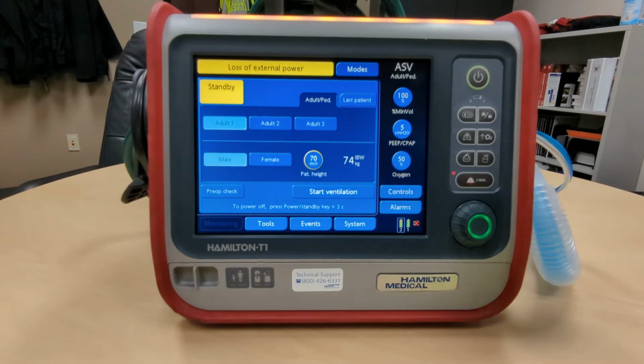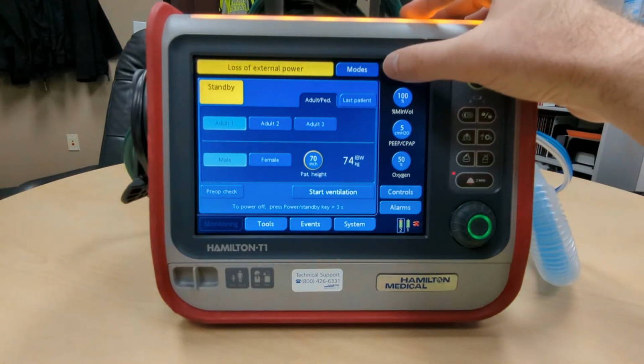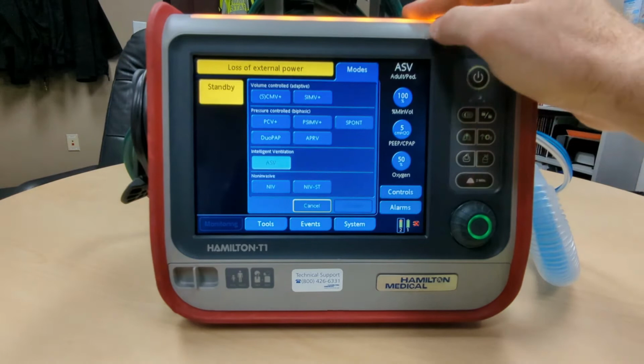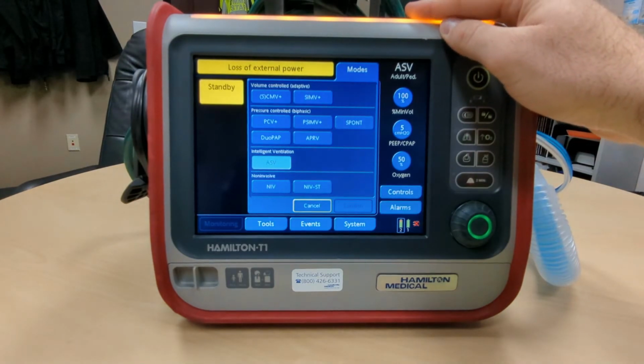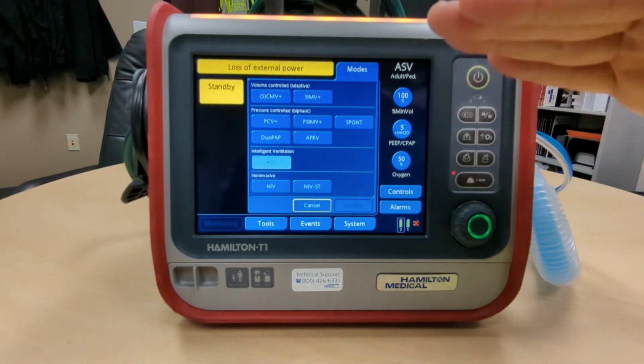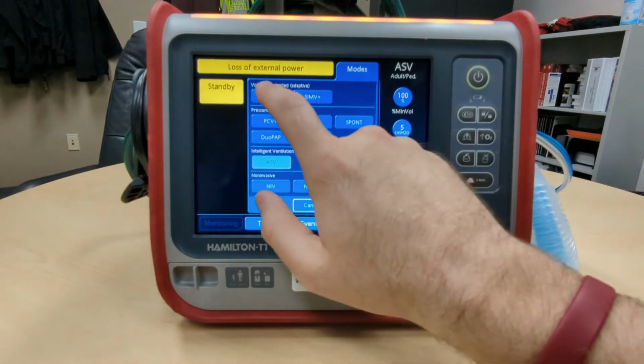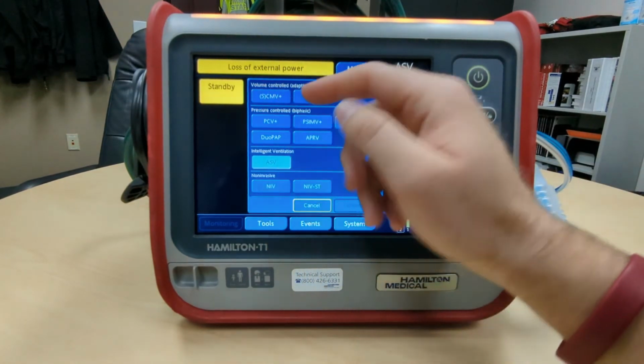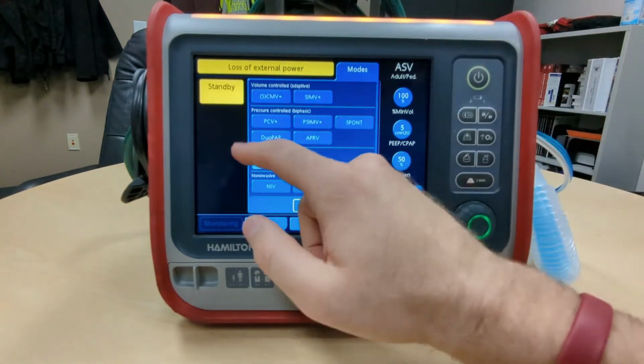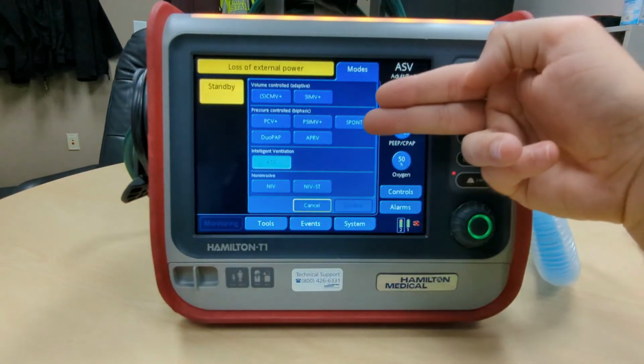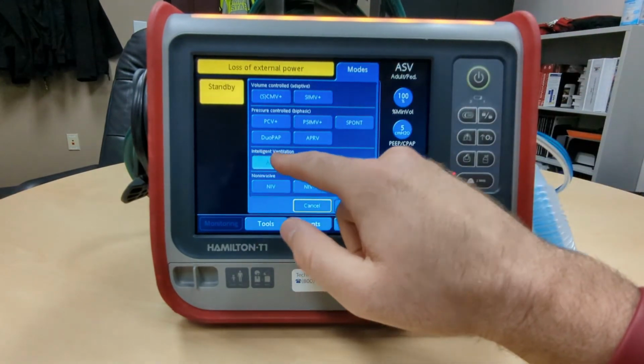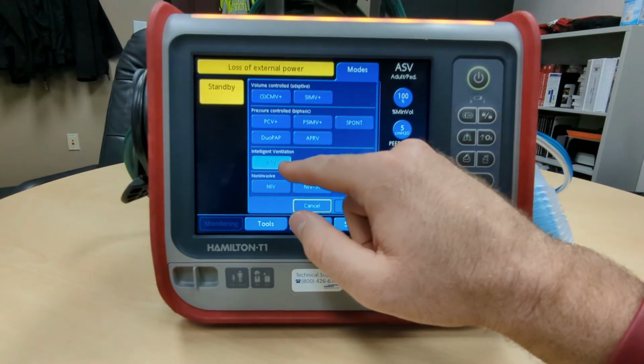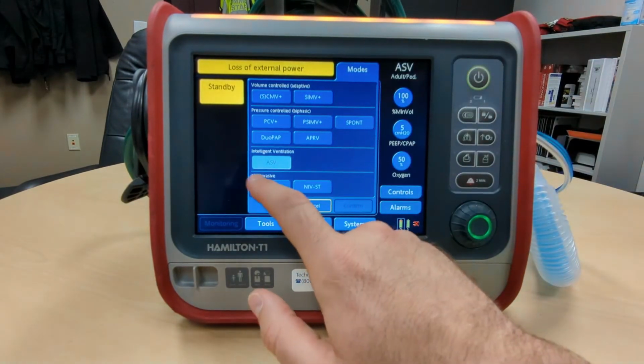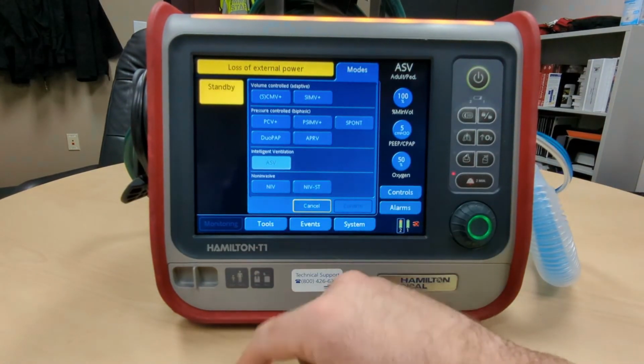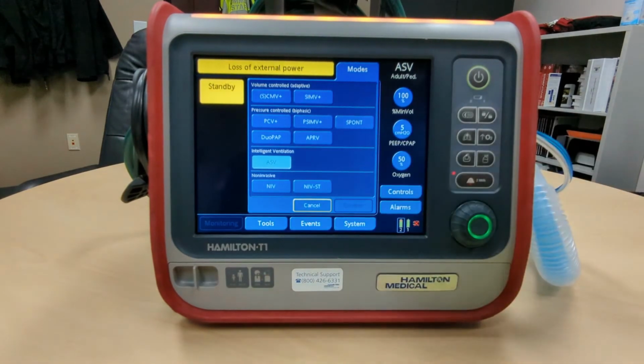For mode selection, the modes button is here on the top right on the screen. Select and it pops up. This is vertically oriented. So see in the white, it says volume controlled adaptive. These are the volume modes. And then pressure controlled biphasic. These are the pressure modes. Intelligent ventilation is just the ASV mode, the automated mode. And then the bottom here is non-invasive, meaning that they are not intubated. So CPAP or BiPAP.